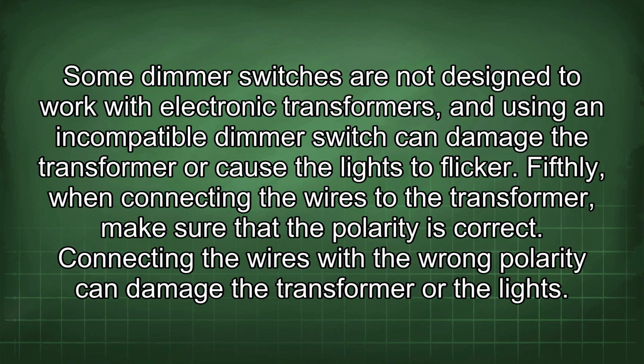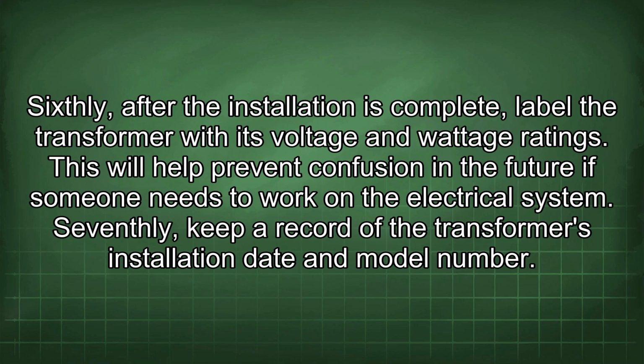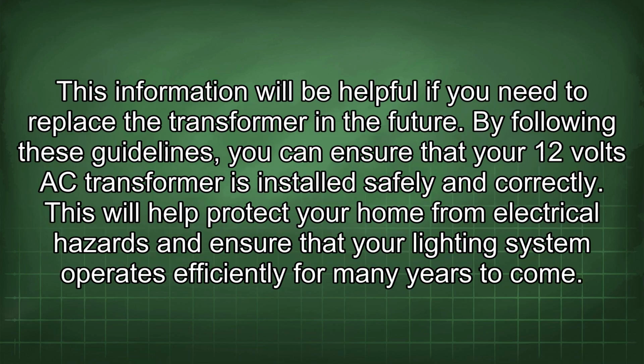Fifthly, when connecting the wires to the transformer, make sure that the polarity is correct. Connecting the wires with the wrong polarity can damage the transformer or the lights. Sixthly, after the installation is complete, label the transformer with its voltage and wattage ratings. This will help prevent confusion in the future if someone needs to work on the electrical system. Seventhly, keep a record of the transformer's installation date and model number. This information will be helpful if you need to replace the transformer in the future.